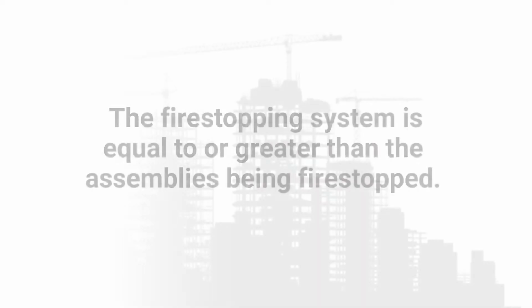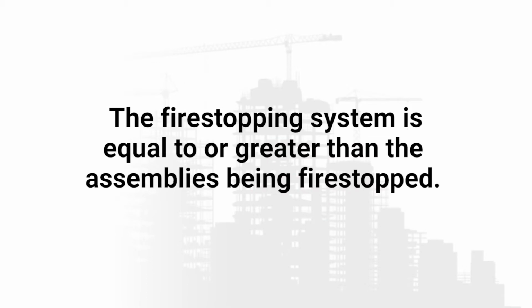While the majority of Firestop systems are UL systems, there are also other independent third-party testing agencies that publish systems for installing Firestop products. It is the details in these tested listed systems that you will be inspecting against. First, always ensure that the rating of the Firestop system to be installed is equal to or greater than the assembly or assemblies being Firestopped.